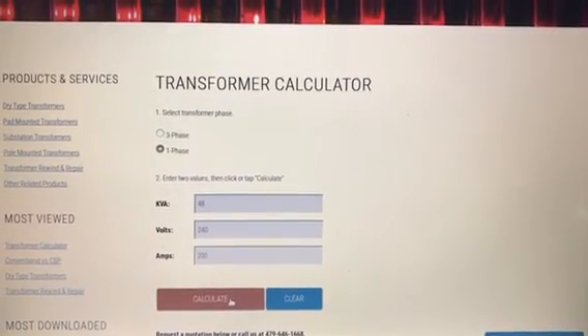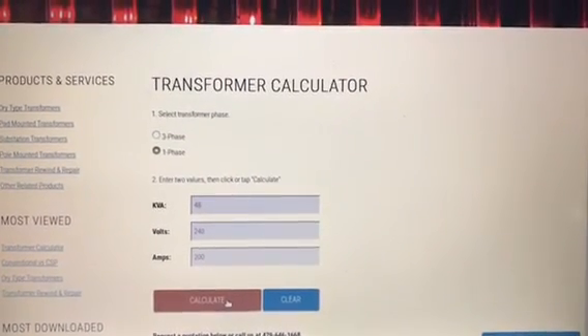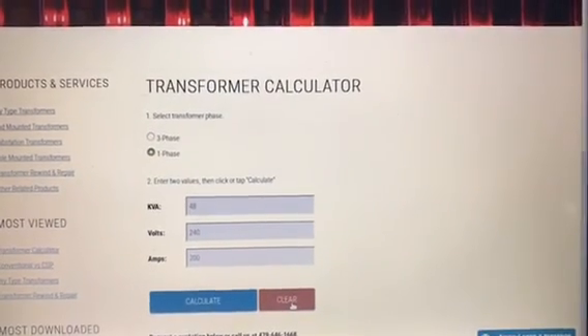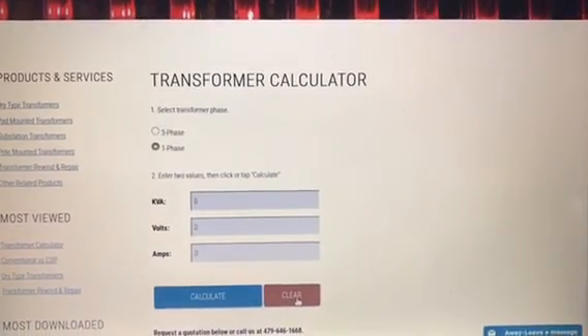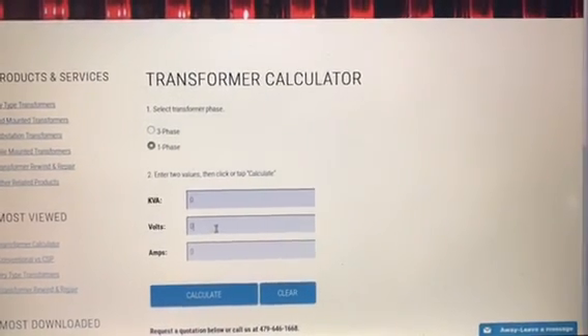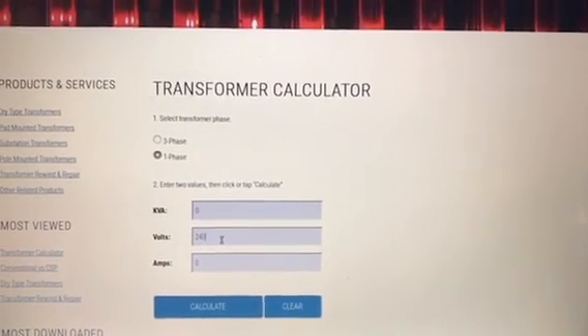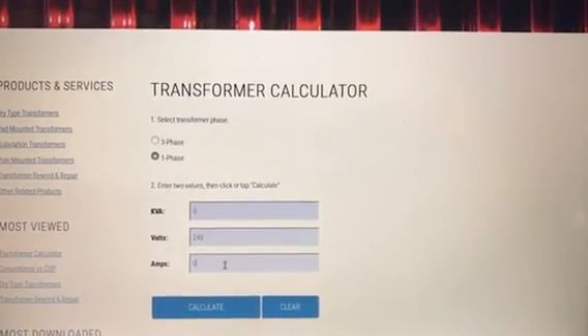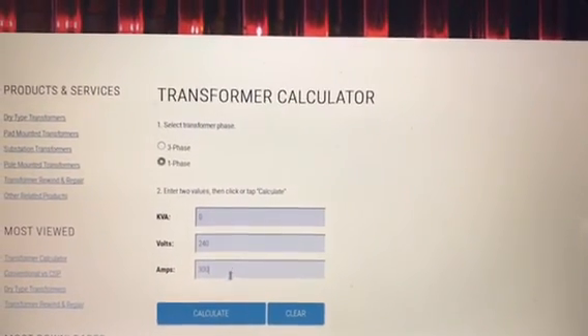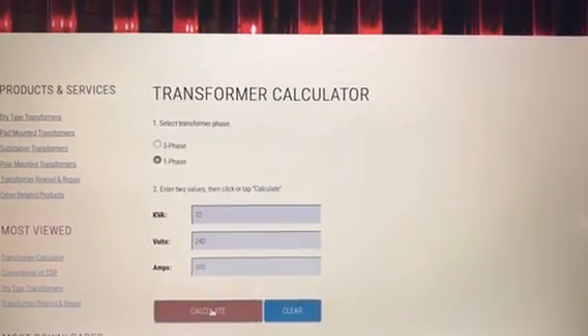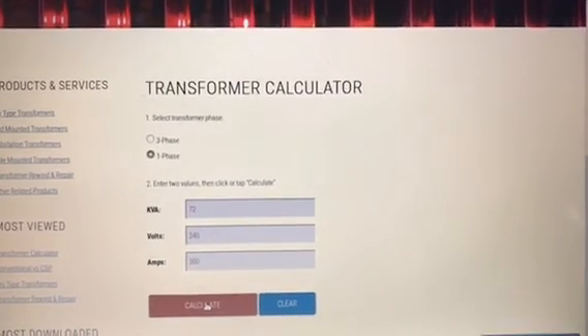Now let's say you're going to have more than one service, or more than one house, connected to this. Let's say you've got a 100 amp service and a 200 amp service. The voltage is still going to be 240 volts, and you're going to have 300 amps now, and you hit calculate, so you should have 72 kVA.